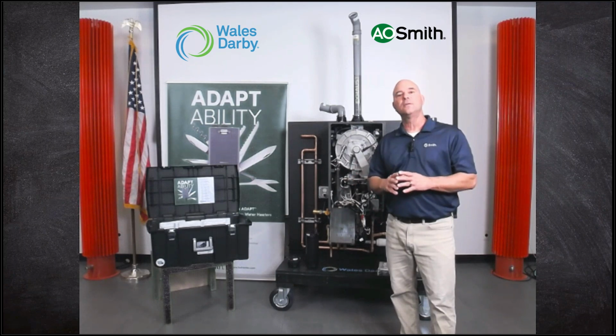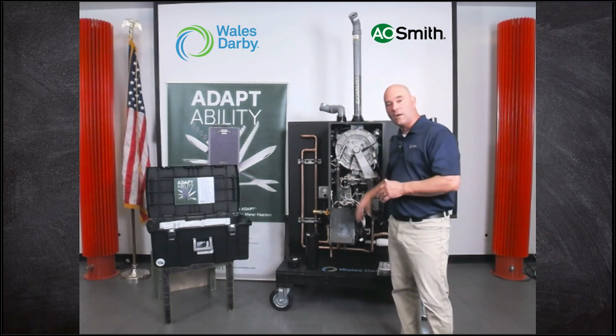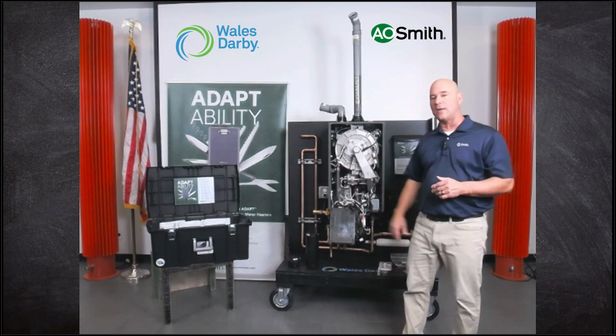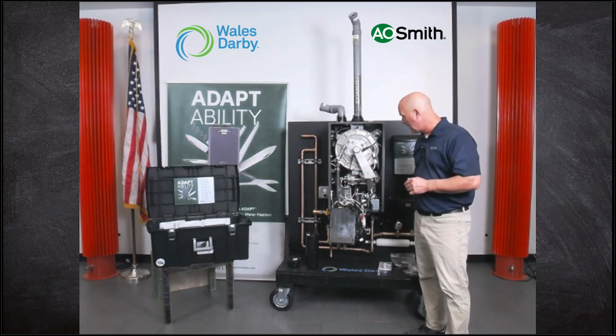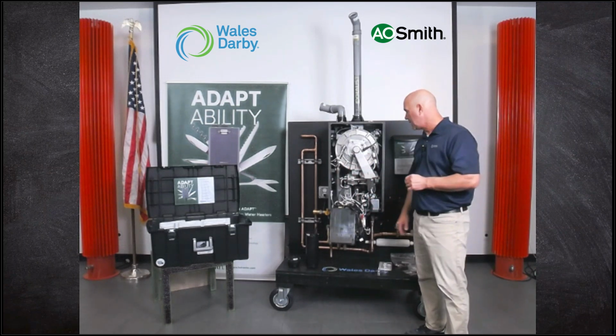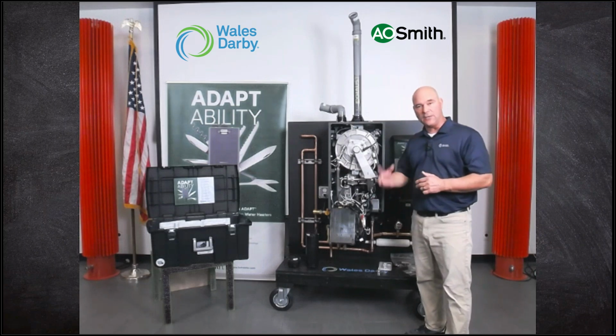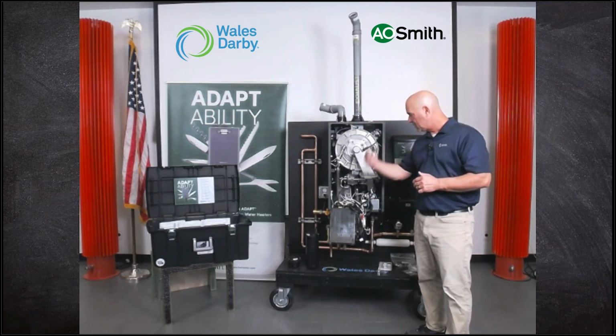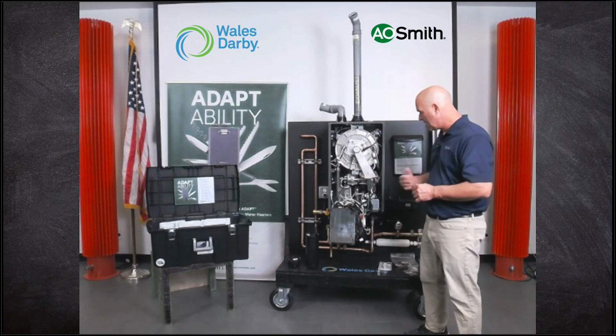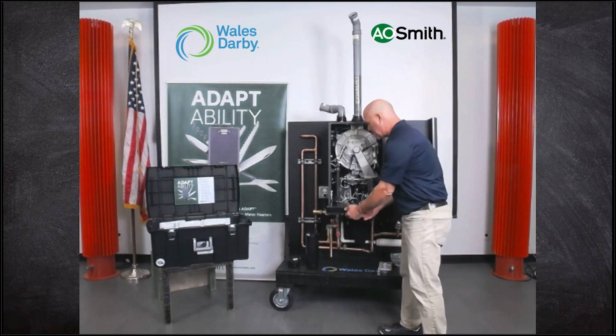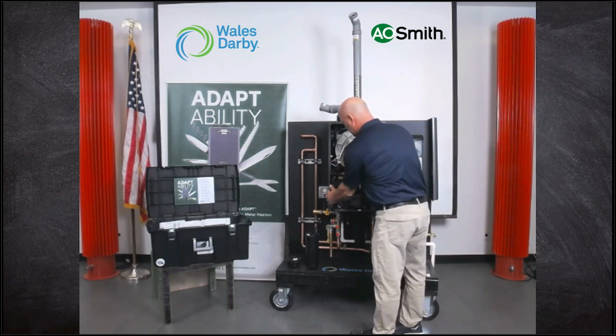Make sure you use the A.O. Smith valve. Most of the other flow valves out there are not high enough to meet our minimum flow rates. So you want to use that A.O. Smith flow valve so we can do a non-dedicated return line and still have recirc. Again, you have the opportunity to put 2 different timing mechanisms in there to have it cycle when you want it to, to make sure you have hot water at every faucet.